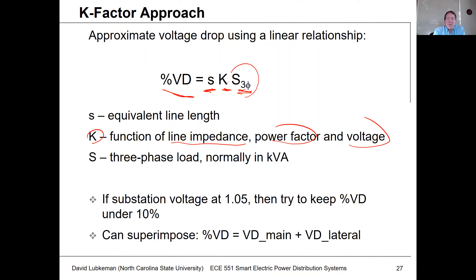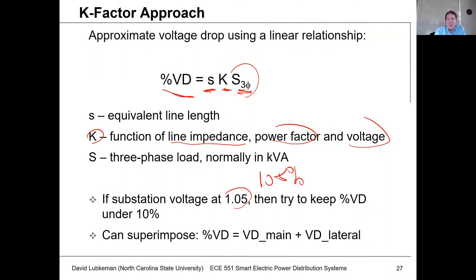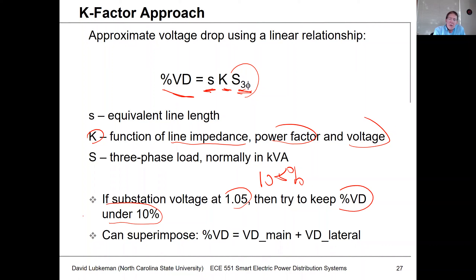If the substation voltage is at 1.05 per unit or 105%, we want to build a system where the voltage drop stays under 10% going from the top of the feeder all the way down to the customer. What's useful about the K-factor is that since this is a linear calculation, we can superimpose results. For example, to calculate the percent voltage drop to a customer, we can superimpose the drop on the main feeder with the drop on a lateral and simply sum those together to get the net voltage drop.